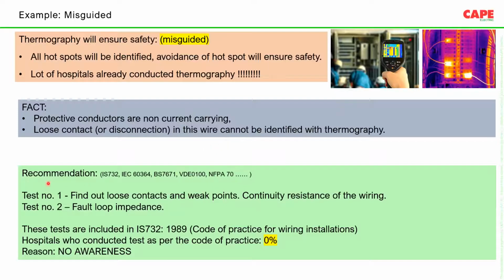Now, if we look at IS 732, IEC, British, American, or whatever the standard, the first test recommended is to find the loose contacts and weak points in a wiring. So continuity resistance measurement is the first test recommended in a wiring. That means after installing the wire through the conduit, you should measure the resistance of the circuit and check whether the resistances are within the limit or not, which we don't do. Number two, fault loop impedance.